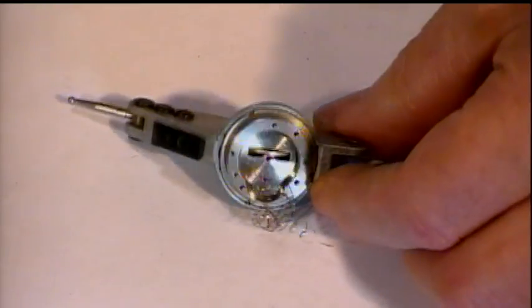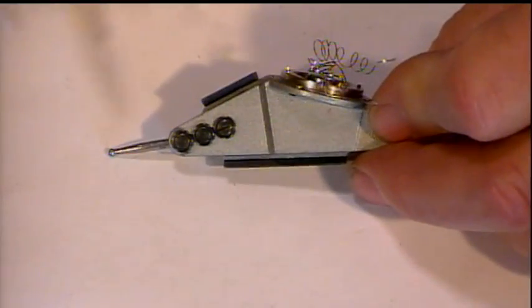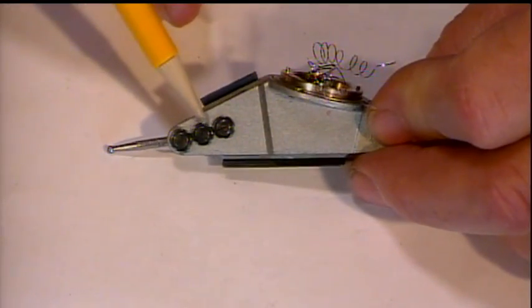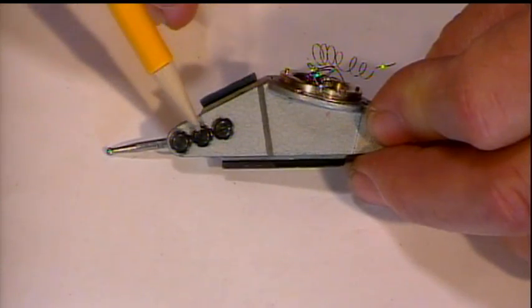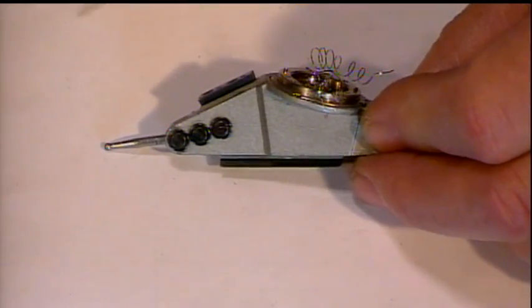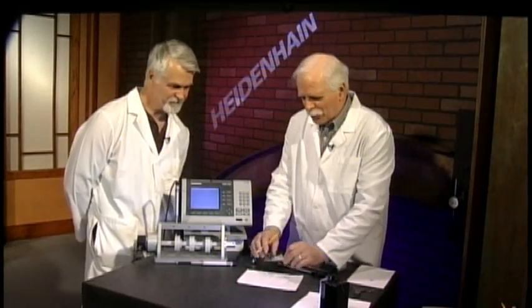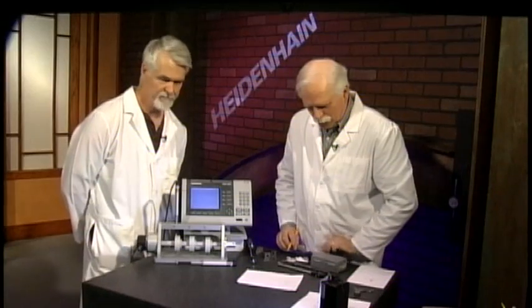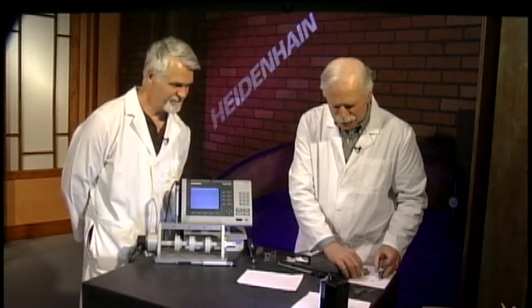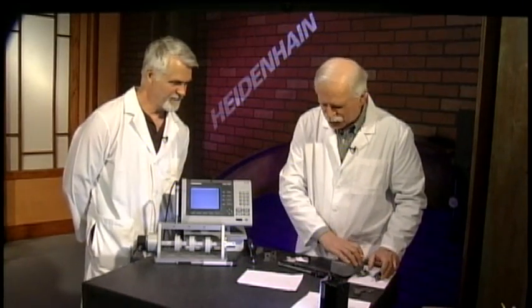The point with this tool was that this particular indicator has three screws - do not touch those. So you couldn't calibrate this one? No. Any of the Interapids - do not touch those adjustment screws at all. If it needs adjustment, you're best off getting it to the calibration lab or to somebody familiar with repairing them.